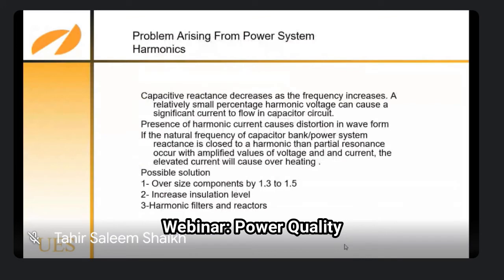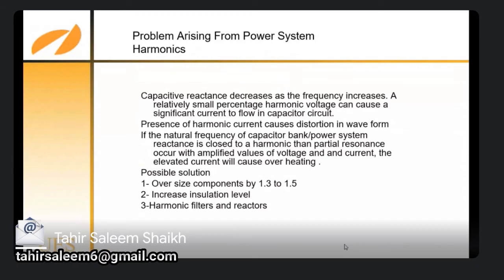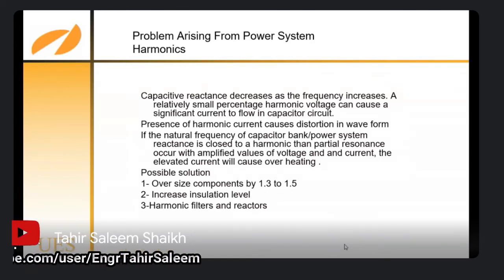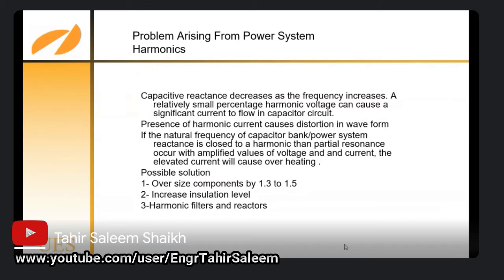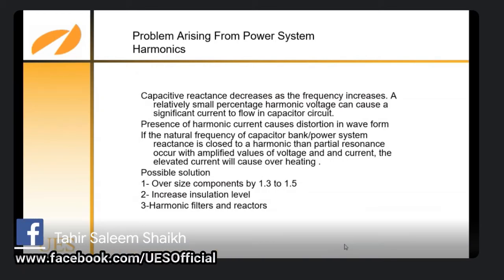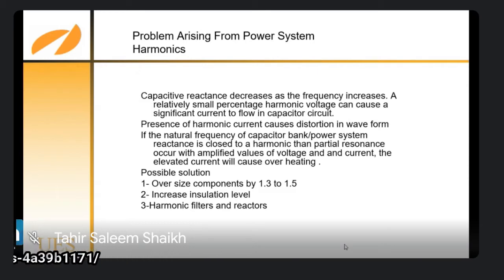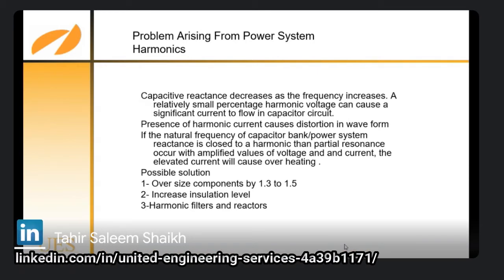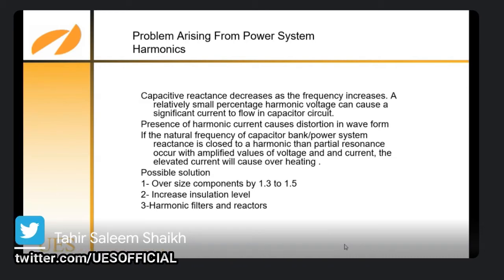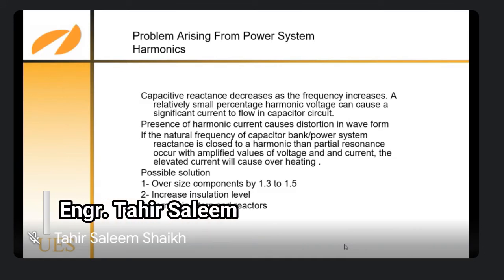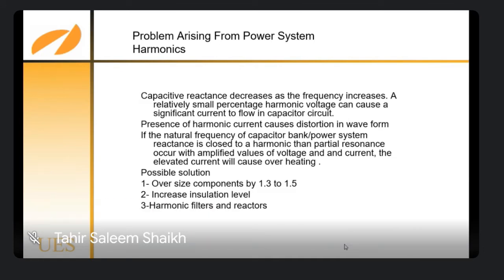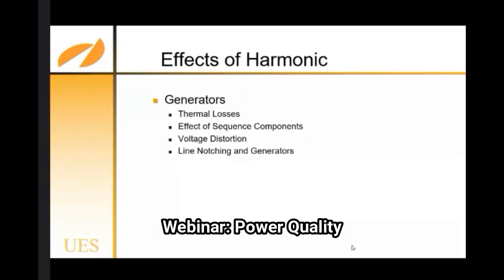We have also discussed that capacitive reactance decreases as the frequency increases. A relatively small percentage of harmonic voltage can cause a significant current to flow in a capacitor circuit. The presence of harmonic current causes distortion in the waveform. If the natural frequency of a capacitor bank and power system reactance is close to a harmonic, then partial resonance occurs with amplified values of voltage and current. The elevated current will cause overheating. A possible solution is to oversize the component by 1.3 to 1.5, and increase insulation levels. It's a common problem.